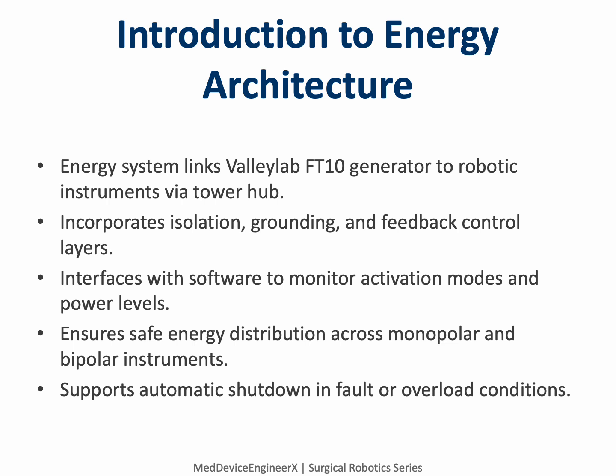Within this chain, isolation transformers, grounding checks, and current limit circuits prevent stray voltage or patient risk. The tower's embedded controllers constantly monitor parameters such as voltage, impedance, and activation time, feeding data back to the console for display. Whether the surgeon activates a monopolar scissor or a LigaSure sealer, the software ensures energy remains within calibrated thresholds. If any irregularity, like abnormal impedance or disconnected electrode, is detected, the system halts output instantly. This multi-layered design turns raw power into a governed, intelligent resource, responsive, yet inherently safe.